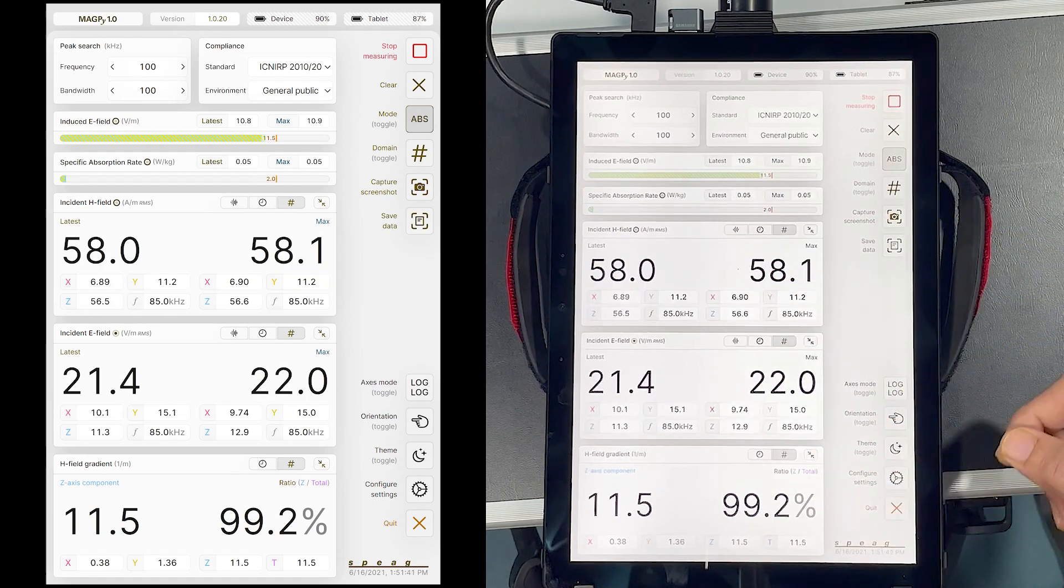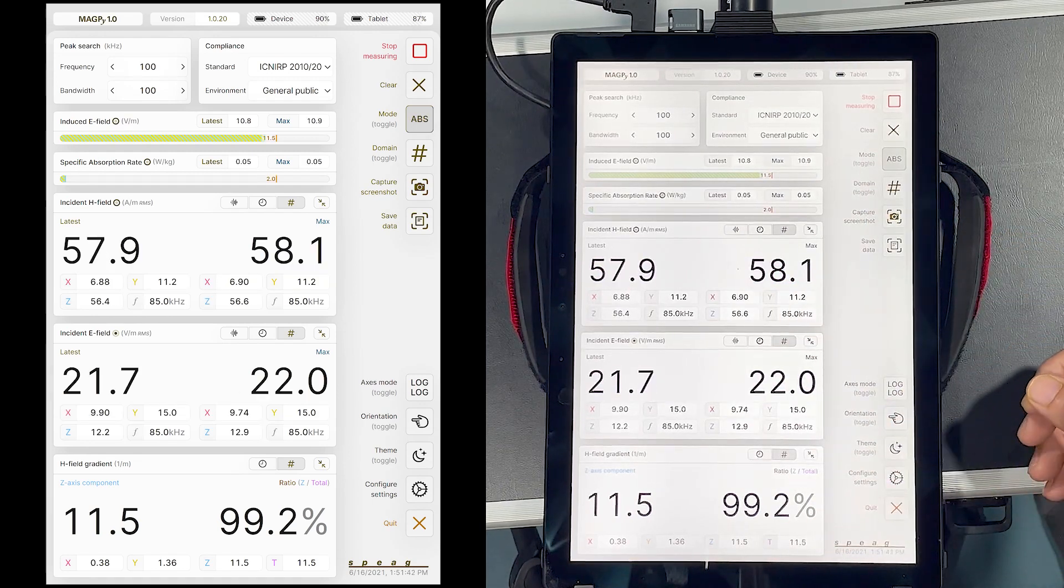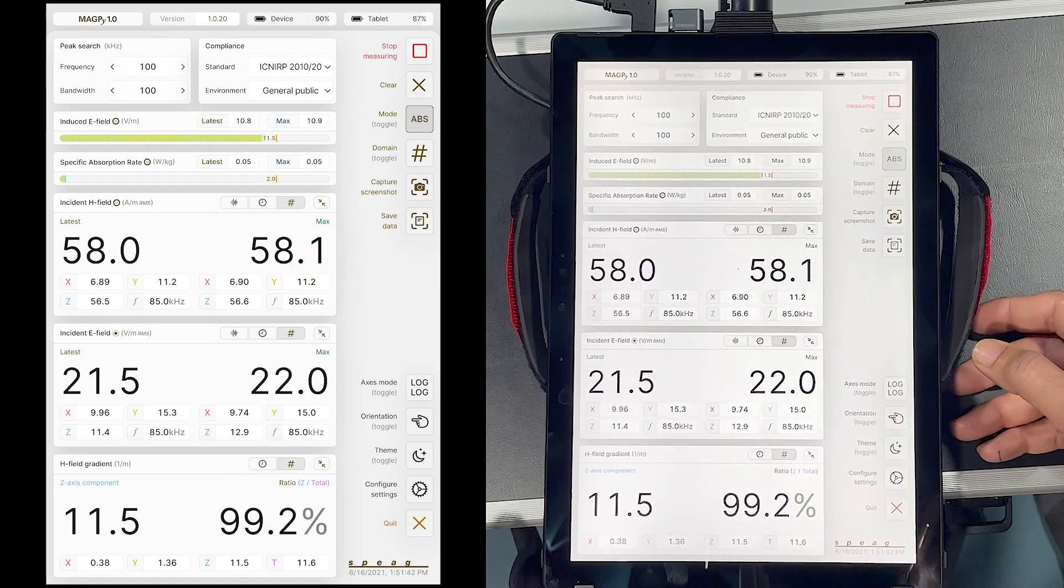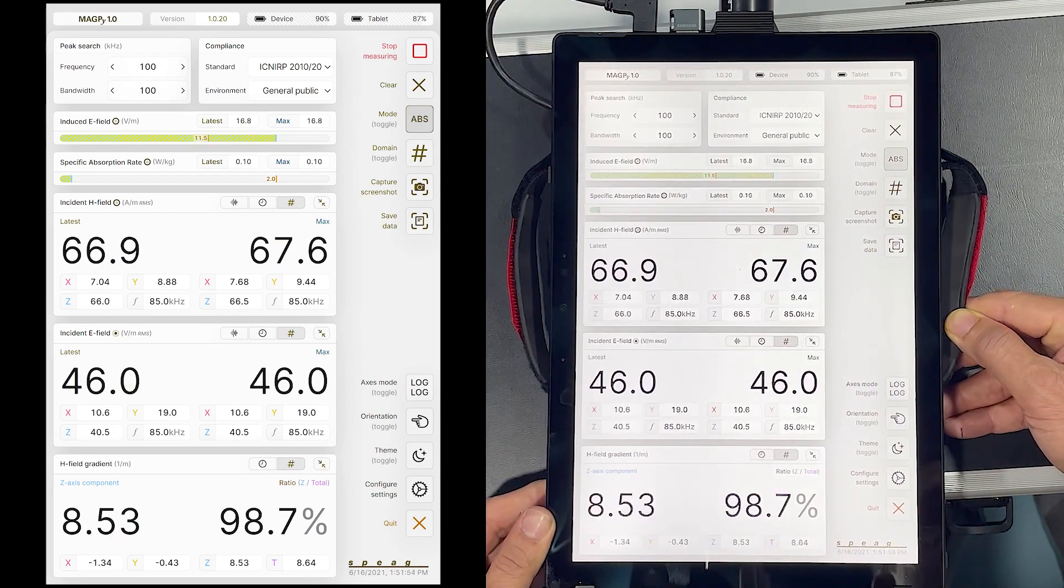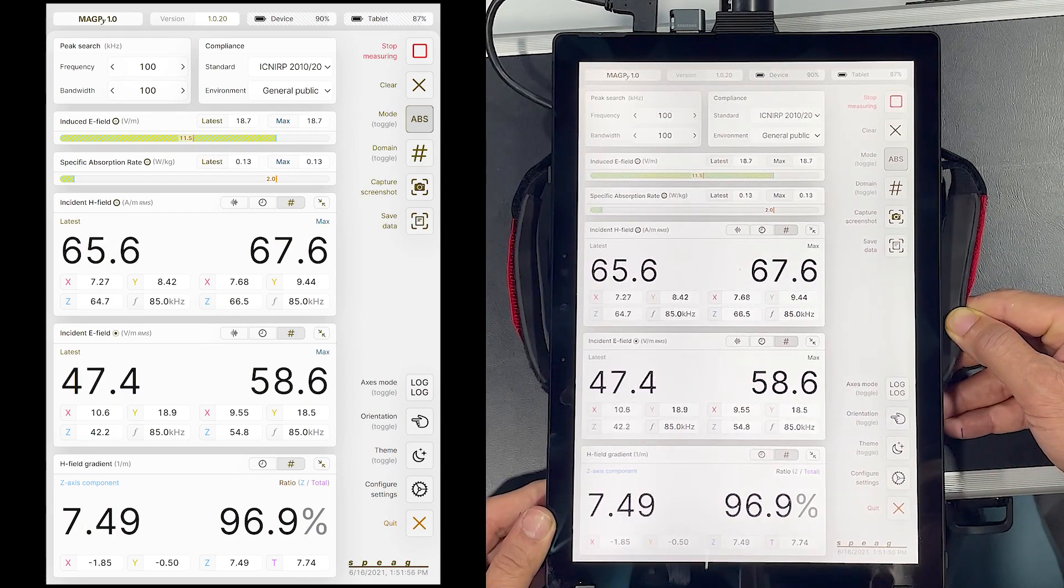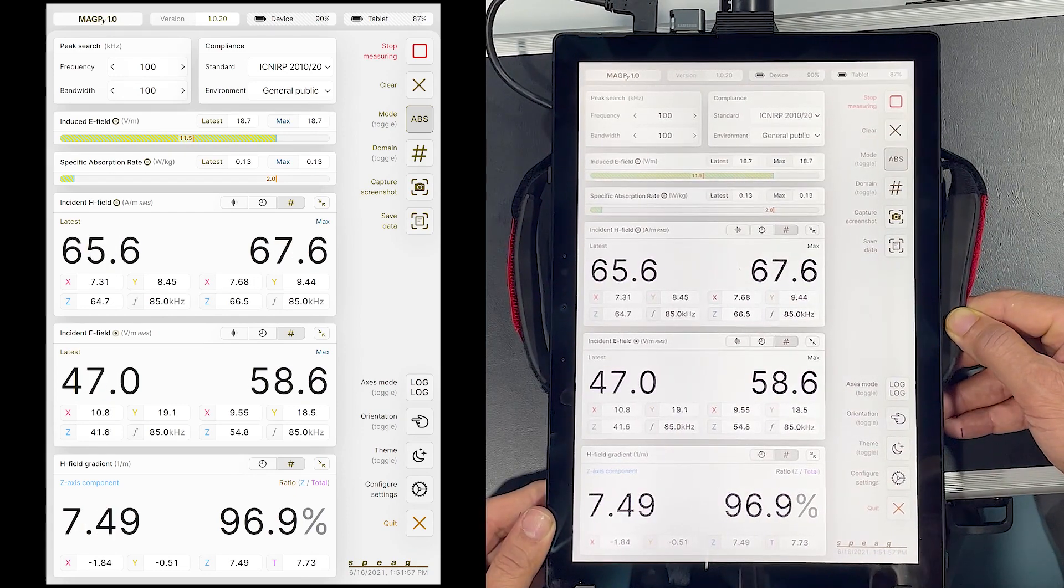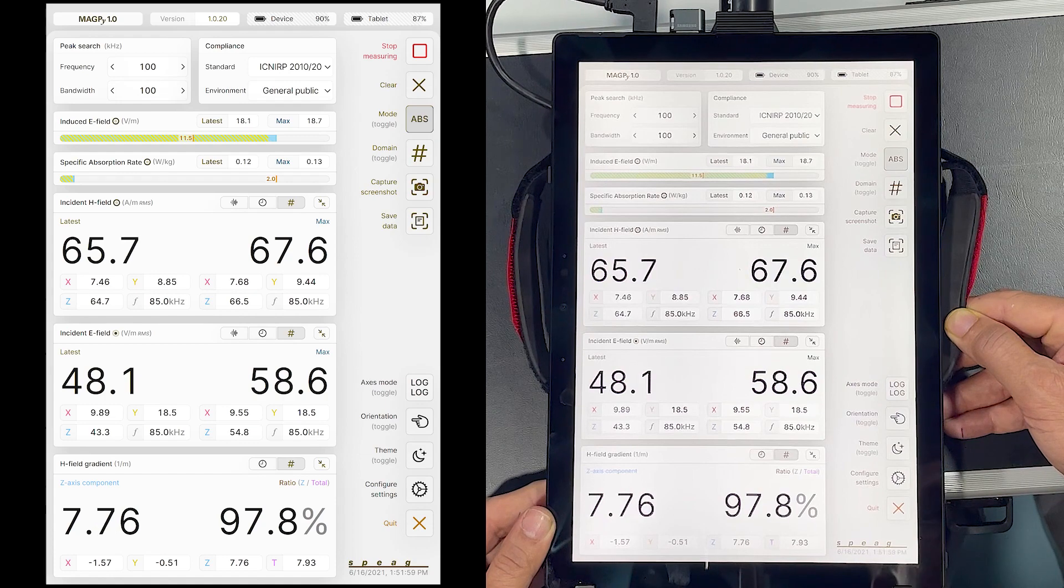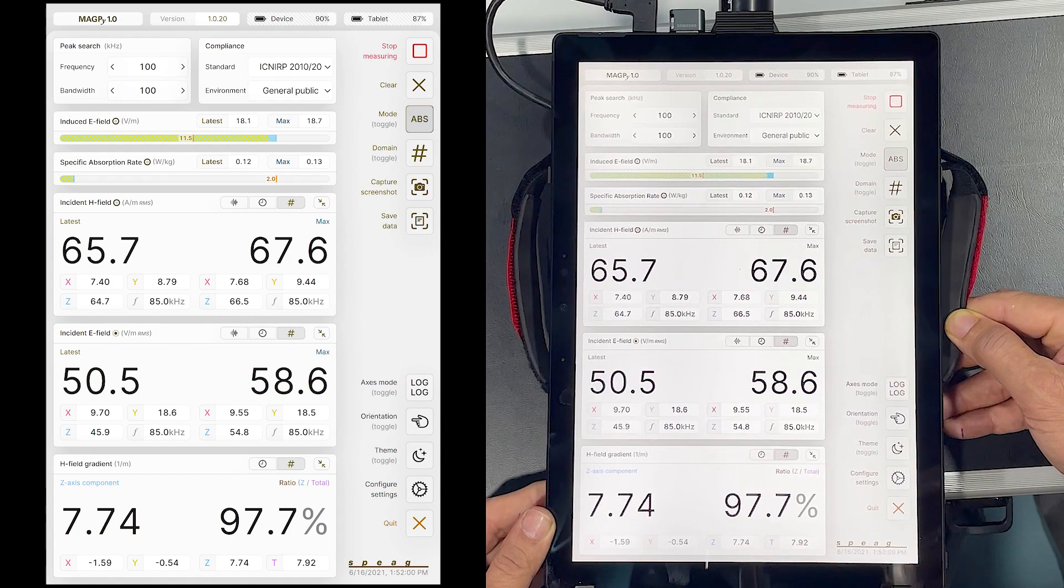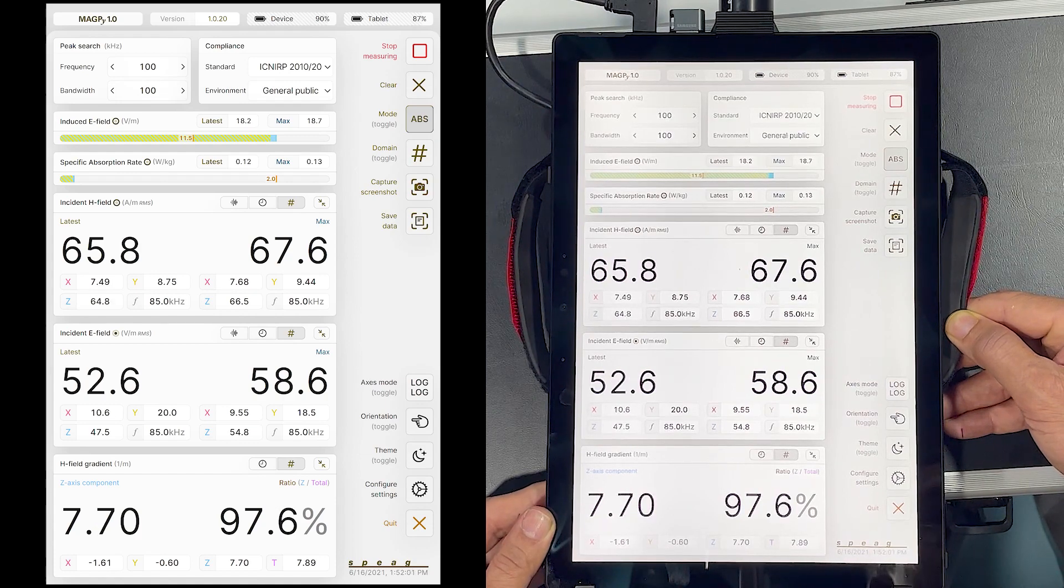The display shows the latest as well as the maximum values for the field. So, I move the device towards the source. The maximum values are updated and as I move back, these remain constant.